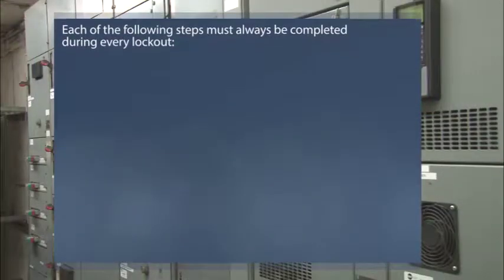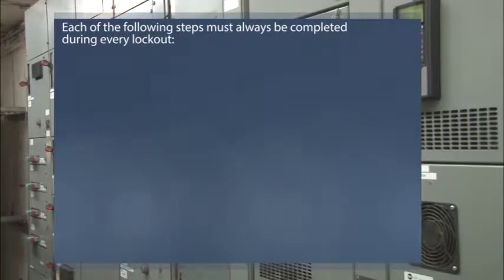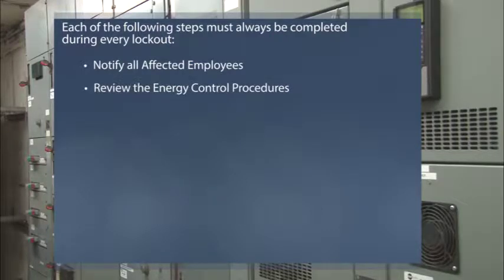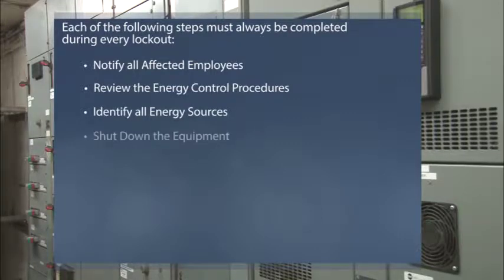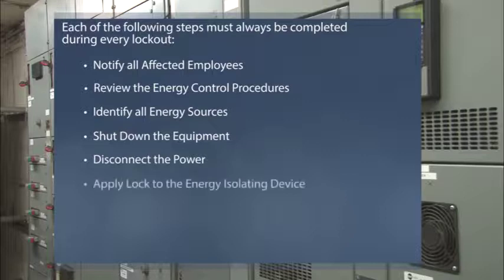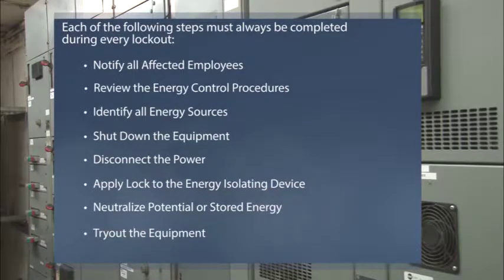To assure lockout, tagout, tryout is performed correctly, each of the following steps must be completed during every lockout. Notify all affected employees. Review the energy control procedures. Identify all energy sources. Shut down the equipment. Disconnect the power. Apply lock to the energy isolating device. Neutralize potential or stored energy. And try out the equipment.